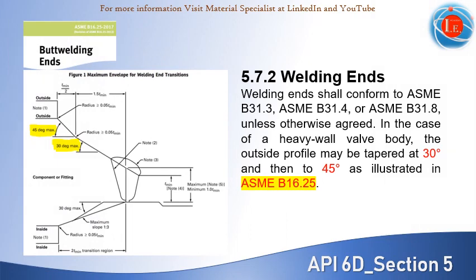API 6D valves may be configured with a flanged end connection or weld end joint. Unless otherwise agreed, welding ends shall conform to ASME B31 piping and pipeline codes shown in this slide. For valve bodies having heavy wall thickness, the outside profile may be tapered at 30 degrees and then to 45 degrees as illustrated in ASME B16.25, as shown on this slide.